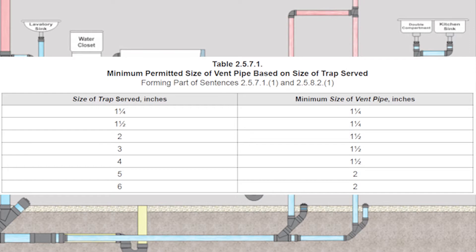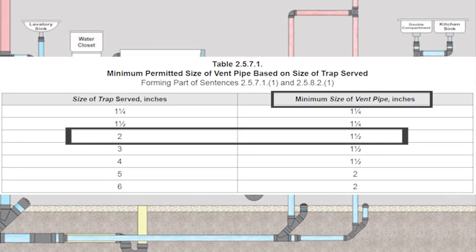The best part about table 2.5.7.1 is that it is very easy to read. If you look on the left-hand column it says the size of traps served. Now we're looking at the clothes washer that has a two inch trap. So I go down to two inches then I go across to the right. Minimum size of vent pipe is one and a half inches.